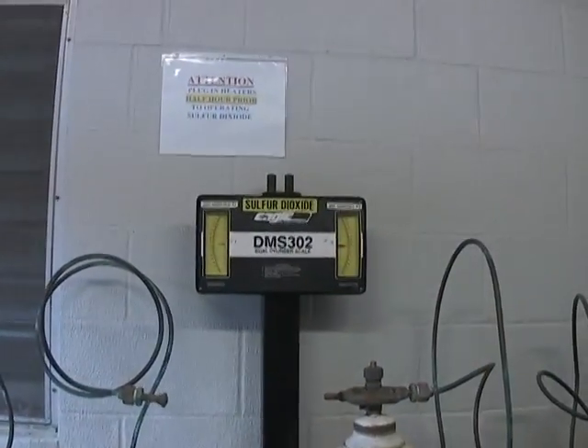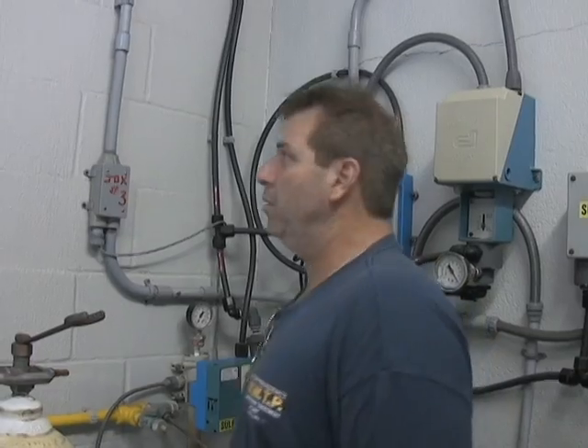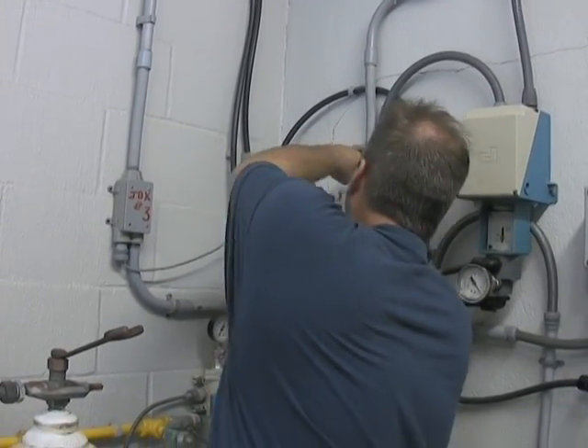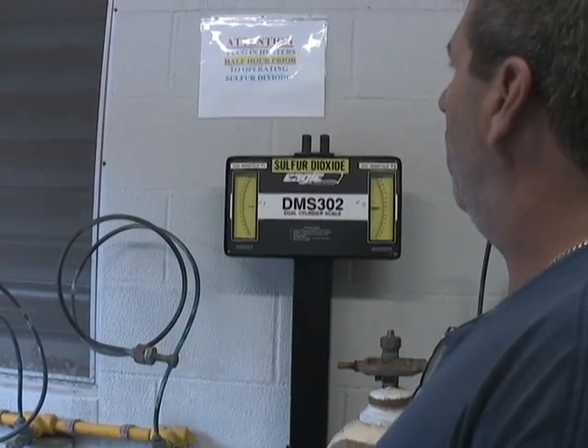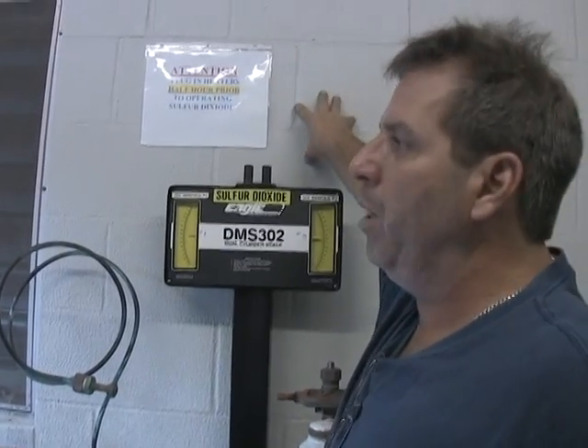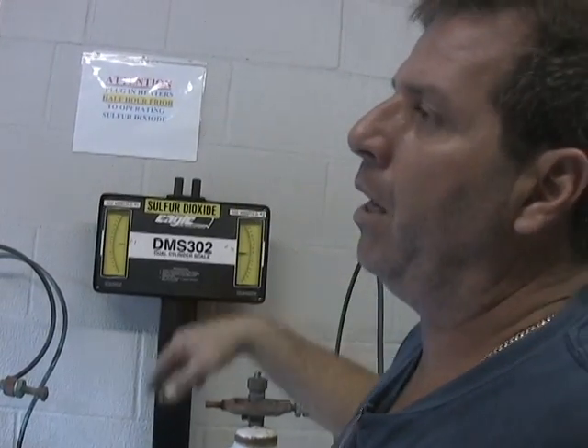To carry this gas, you have to have these heaters for the gas to be effective. So this one's plugged in right now. It really should be unplugged because there's no sense in keeping these on if we're not going to be using the gas. If we know we're going to have a hypo event, a discharge event, we'll turn the hypo on, and it's induced just past the secondary clarifier. And when you come in, you want to plug the heater in at the side you're going to use. If you don't have that heater on, this is not going to work.